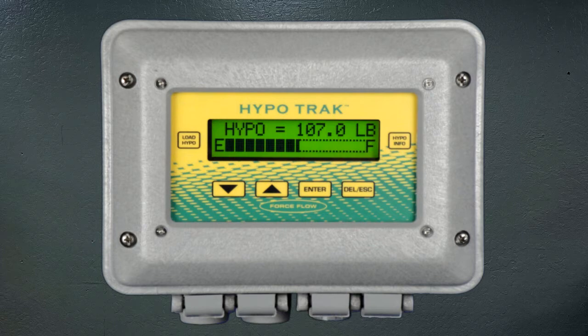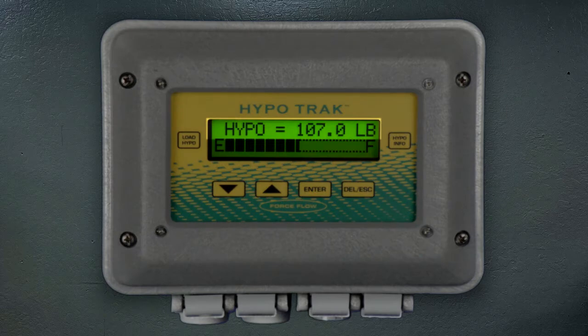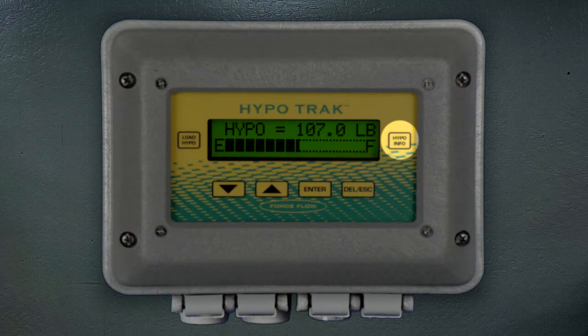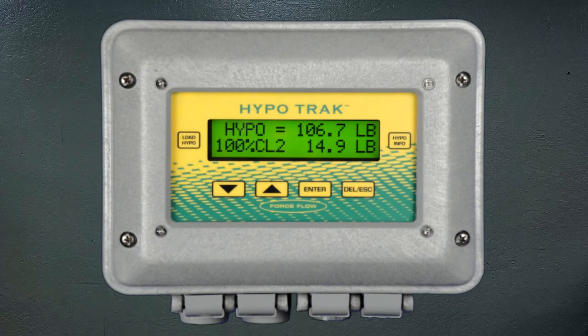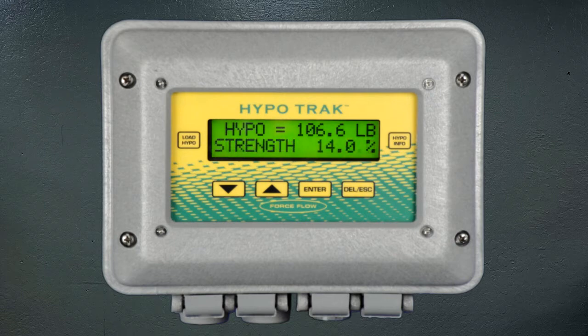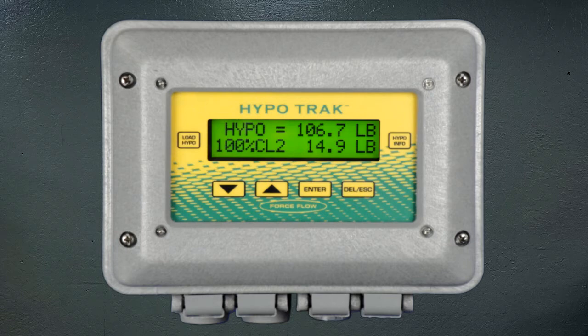Next, I'd like to discuss the various types of information that you can retrieve from the HypoTrack's display. At all times, the top line receives a signal from the scale or ultrasonic level sensor to display in pounds or gallons how much Hypo is remaining. With your degradation curve selected and a beginning strength entered, the following information is available: a bar graph showing how full your tank is, your Hypo expressed as 100% pure chlorine gas, how old your Hypo is in number of days, the current strength of your Hypo, and the current Hypo feed rate. The 100% pure function is handy for those who want to track their Hypo usage in terms of total oxidant fed.